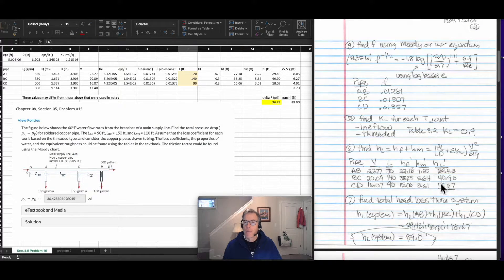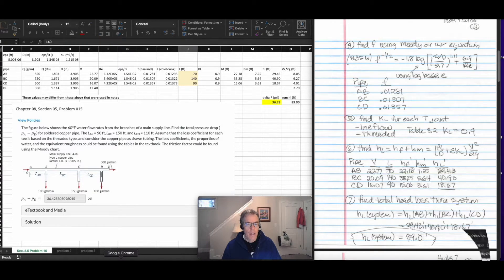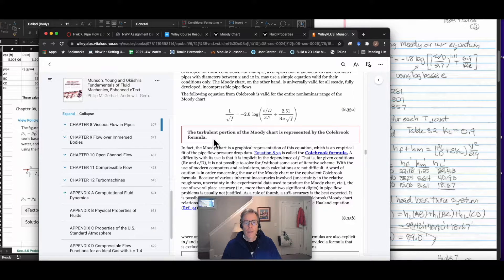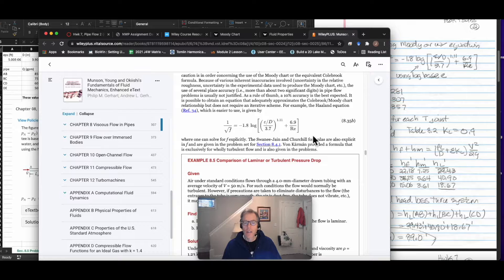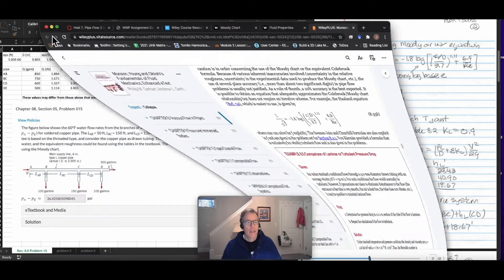Next, I used the Moody diagram or an equation. Now that I know the Reynolds number and the relative roughness, I can find the friction factor f. You can look that up in the Moody diagram. I chose to use one of these equations from the textbook. The turbulent portion of the Moody chart is represented by the Colebrook formula, which is not an explicit equation — the friction factor you want to calculate is itself a function of the friction factor. So I chose to use another equation called the Haaland equation, which is an approximation of the Colebrook equation that gives you an explicit result.